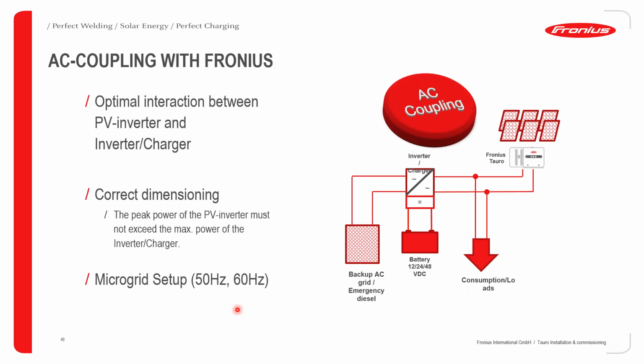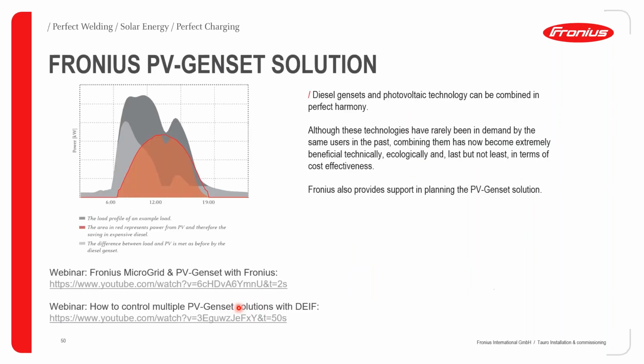The reason for this is that the Tauro will come standard with MG50 or MG60 country setup. The Tauro will also be compatible with PV-GENSET solutions. The reason for this is due to the MG50 and MG60 country setups. So again, if you're having these very big 1 megawatt, 2 megawatt installations, off-grid type installations where there's a generator on site and they want to add solar, to cut down the cost of diesel, this is also possible. So the solar will be active if there is any grid available, okay, and if the grid does go down and the genset comes up, the solar will also be active in order to decrease the amount of diesel that you're using.